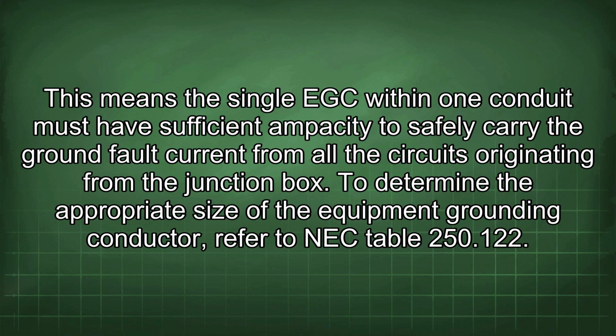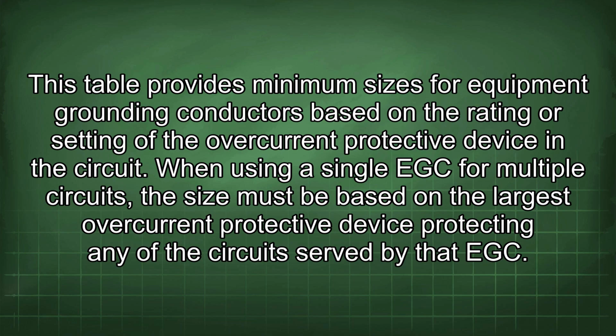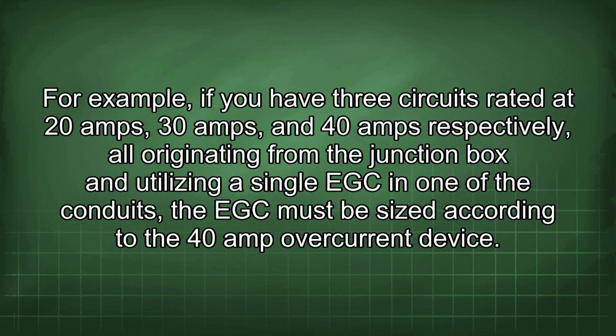To determine the appropriate size of the equipment grounding conductor, refer to NEC Table 250.122. This table provides minimum sizes for equipment grounding conductors based on the rating or setting of the overcurrent protective device in the circuit. When using a single EGC for multiple circuits, the size must be based on the largest overcurrent protective device protecting any of the circuits served by the EGC. For example, if you have 3 circuits rated at 20 amps, 30 amps, and 40 amps respectively, all originating from the junction box and utilizing a single EGC in one of the conduits, the EGC must be sized according to the 40 amp overcurrent device.